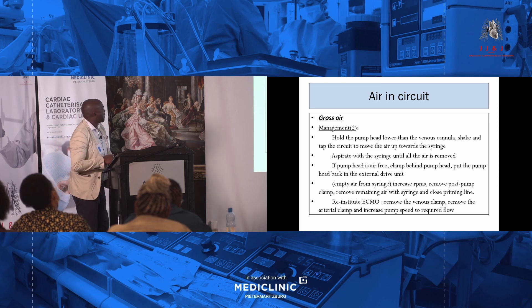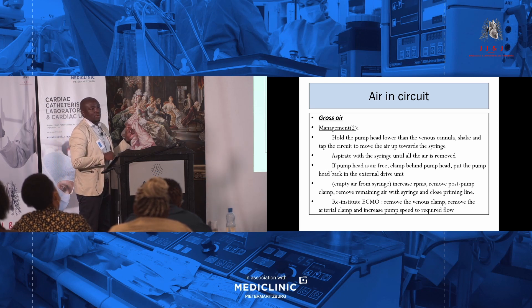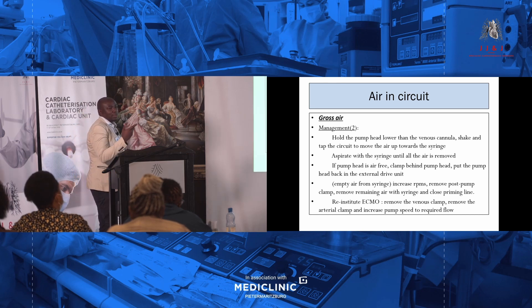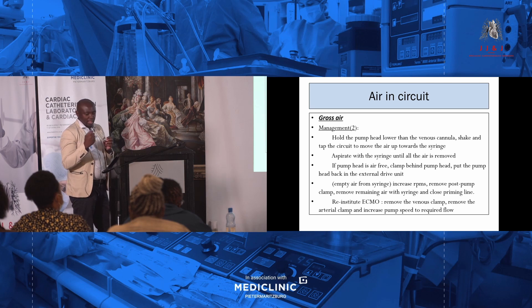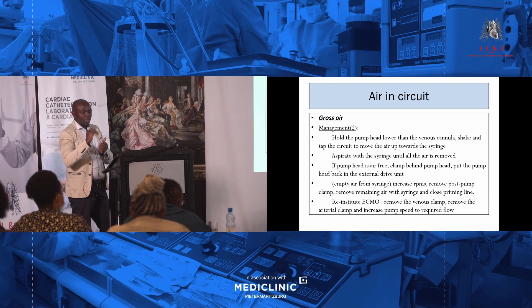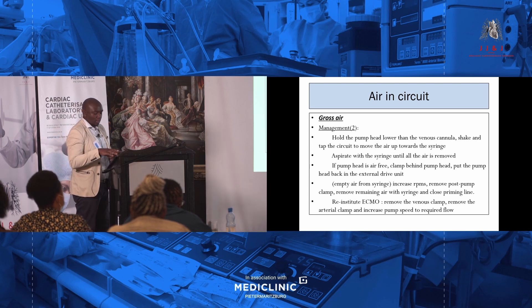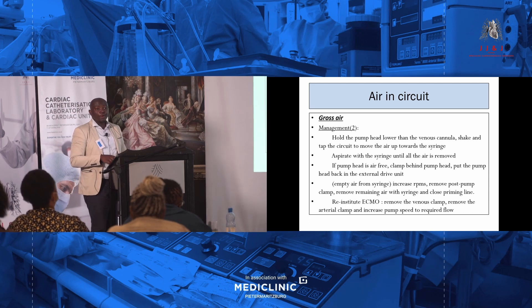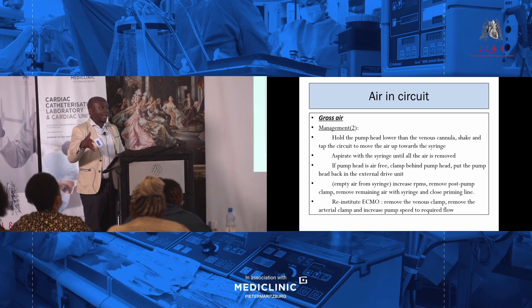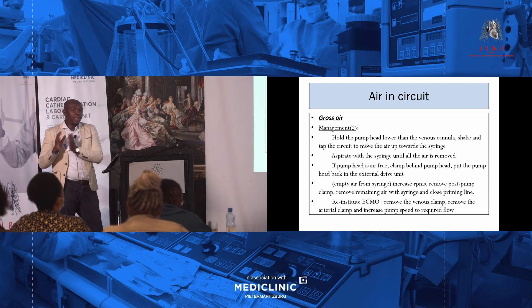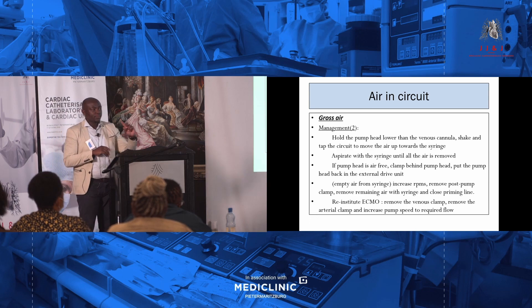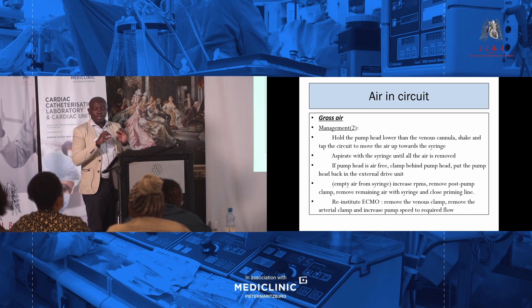I'll ask both companies to help introduce air into the circuit during the practical session, because you need to sit very close. We'll first introduce the big bubble — you'll see what happens: the machine trips and stops. With smaller bubbles, it will just keep alarming. From experience at Hilton, I'll get a call saying the machine is alarming — what do I do? The nurses need to know when to act and when to leave the machine alone, both on the NovaLung and the Maquet system. The bubbles are small enough — the flow circuit will let them through.